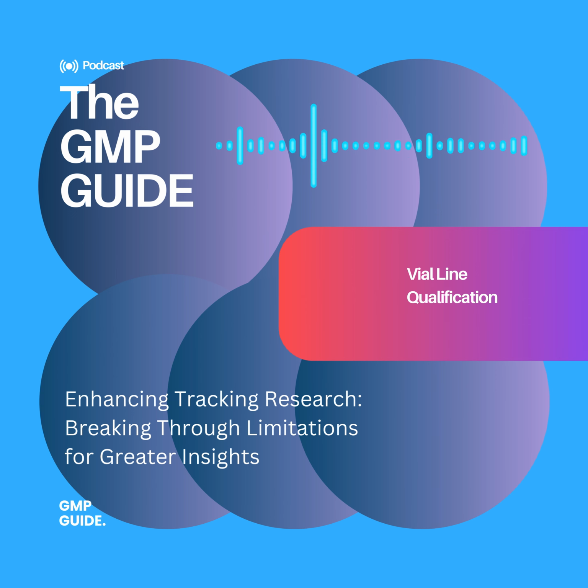Installation Qualification, IQ. Let's start with Installation Qualification, or IQ. After all the equipment has arrived, its purpose here is to meticulously verify that every single piece of equipment, all associated piping, software, and instruments are correctly delivered, installed, and configured.